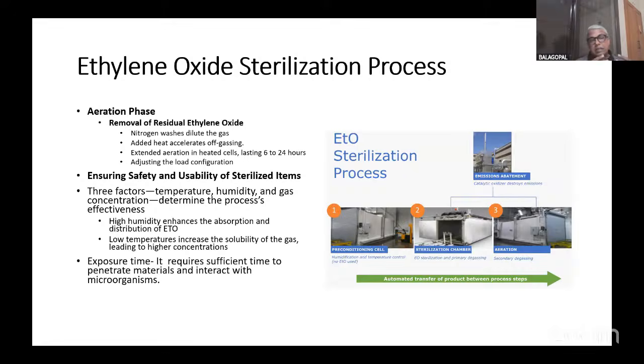The next phase after sterilization by the introduction of the gas is the aeration phase, which involves removal of the residual ethylene oxide. There are different ways of doing it: nitrogen washes, which dilute the gas; added heat, which accelerates the degassing; and extended aeration time in heated cells lasting from 6 to 24 hours. This ensures the safety and usability of the sterilized item.